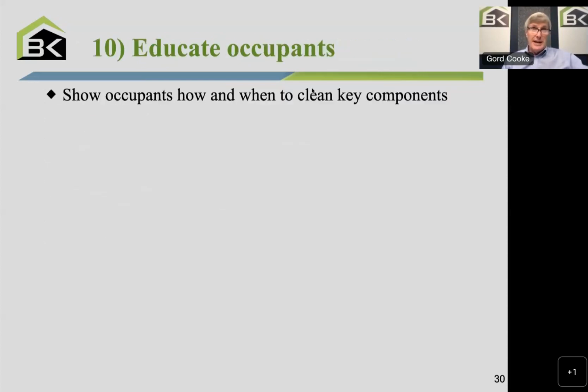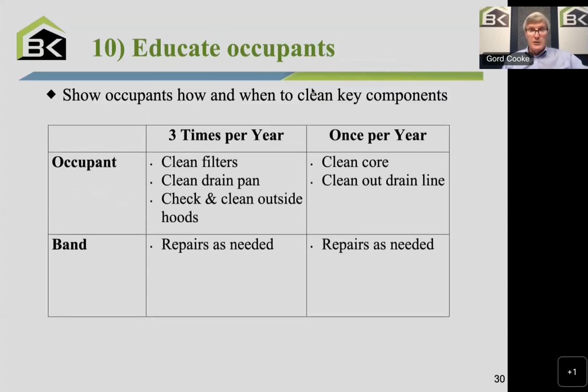And then I would say, lastly, let's show the occupants how and when to clean key components. And you had it right, Claude. It's 3 times a year. Clean the filters, clean the drain pans, check and clean the outside hoods. Once a year, clean the core. At most, maybe clean out the drain lines once a year.